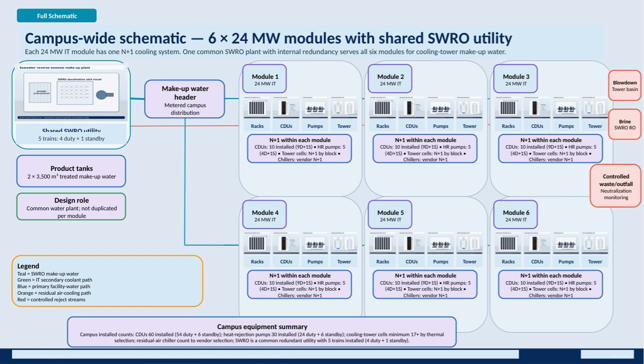Within each 24 megawatts IT module, we have an N+1 configuration, including 10 CDUs installed with 9 duty units and 1 standby, 5 heat rejection pumps set up as 4 duty and 1 standby, cooling tower cells designed with N+1 redundancy by block, and chillers selected to vendor-specified N+1 criteria. This setup is replicated consistently across all 6 modules, maintaining uniform reliability standards. Additionally, tower blowdown and SWRO brine are managed carefully, with controlled neutralization and monitoring to handle waste outfall responsibly.